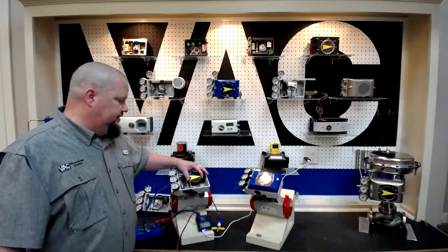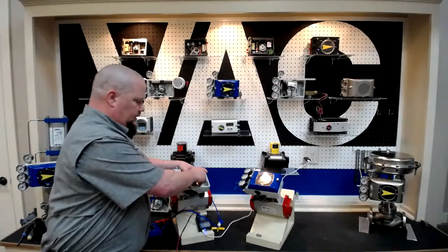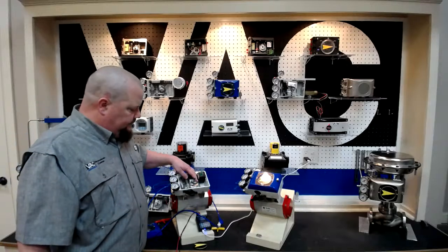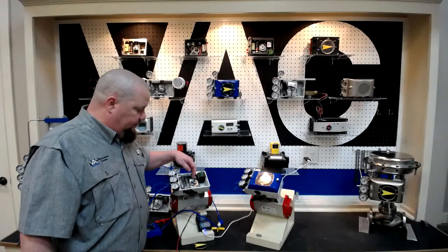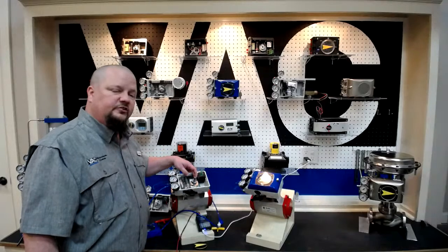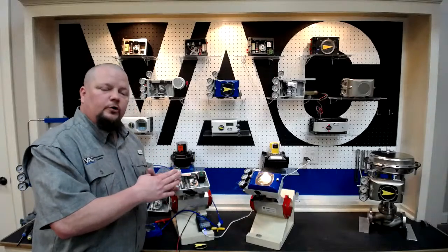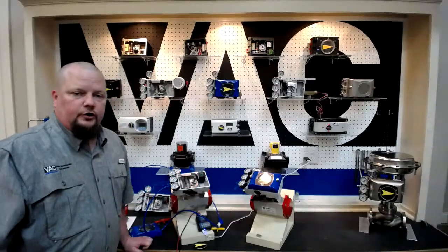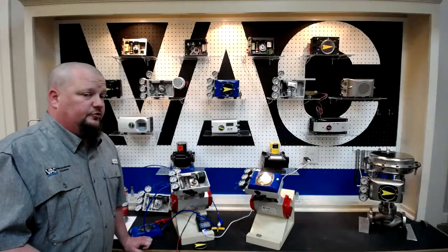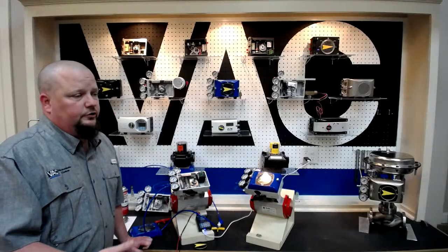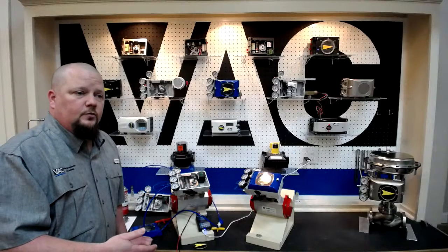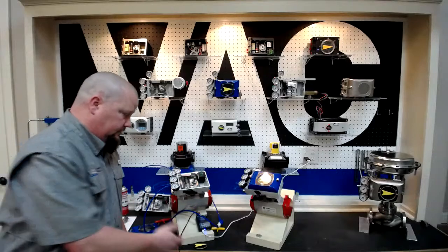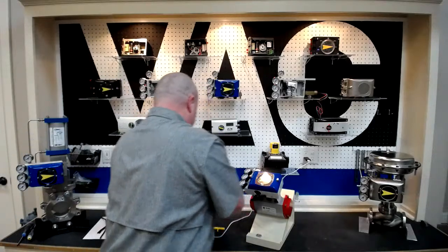The most common issue we see: I'm going to go ahead and remove the indicator. We've removed the cover. I'm going to remove the little arrow indicator on our cam. Oftentimes, we've gone through the video. Oftentimes what happens is this cam is set on the wrong side. We know that there's a little roller bearing, and then it seats right up against the point, and there's a 0 and 100%. If you have it set on 0% and you have it rotating the wrong way, oftentimes it'll jump over the lobe and it won't operate properly. And I'm going to demonstrate how this positioner acts in that circumstance.